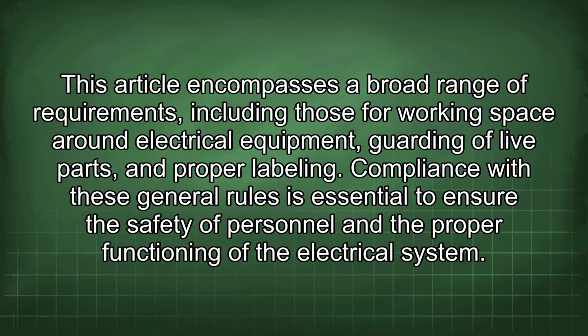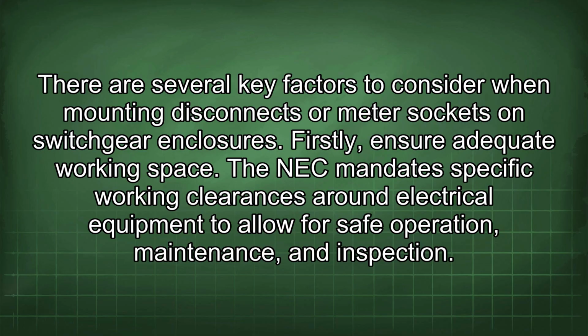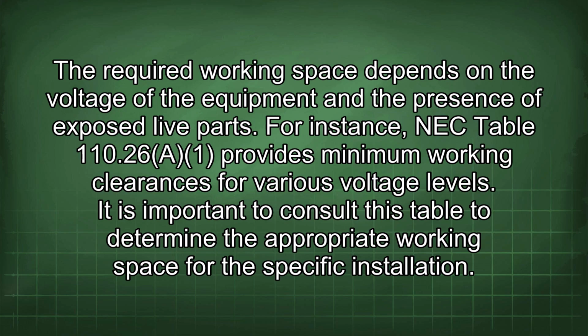Compliance with these general rules is essential to ensure the safety of personnel and the proper functioning of the electrical system. There are several key factors to consider when mounting disconnects or meter sockets on switchgear enclosures. Firstly, ensure adequate working space. The NEC mandates specific working clearances around electrical equipment to allow for safe operation, maintenance, and inspection. The required working space depends on the voltage of the equipment and the presence of exposed live parts. For instance, NEC Table 110.26(A)(1) provides minimum working clearances for various voltage levels. It is important to consult this table to determine the appropriate working space for the specific installation.